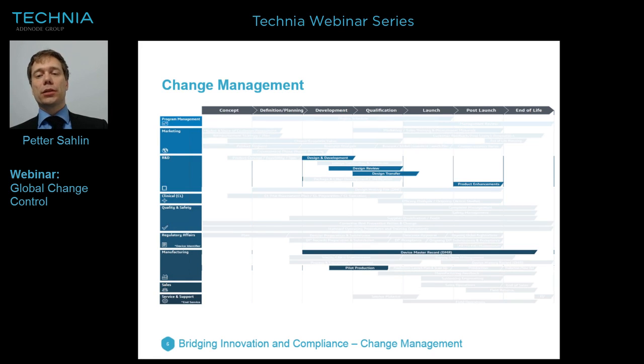So assume that I've launched a CAPA, I've understood the CAPA and I realize this is a change required to implement this CAPA, then this is the change procedure I'd like to run through and go through. For the DMR, this is the traceability on the DMR which I have with me all through the design. And the whole essence here is to have a complete sync between the EBOM and the DMR. So whatever changes I perform, those are always reflected immediately into the device master record.